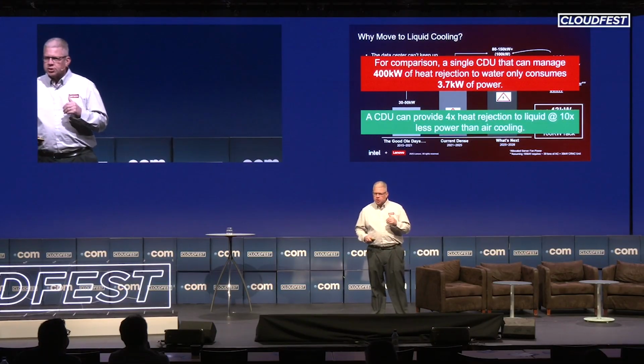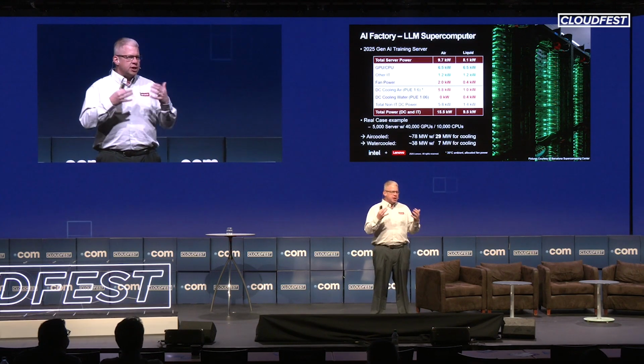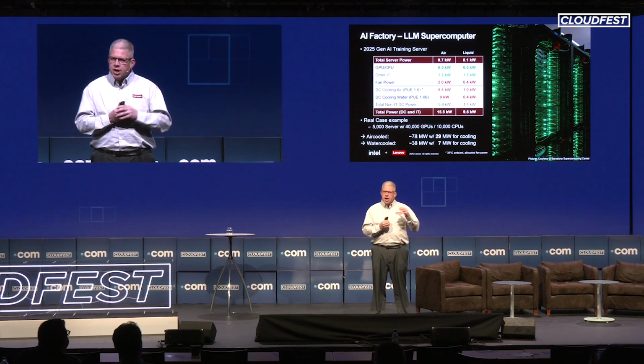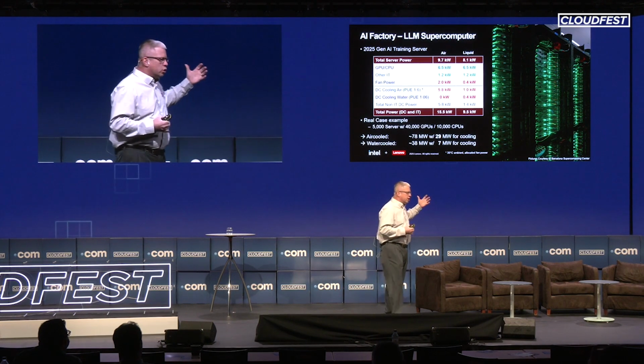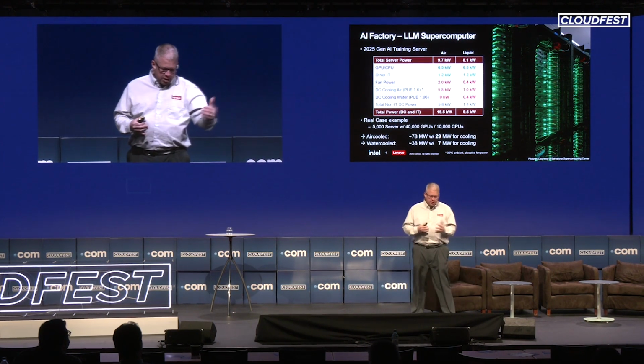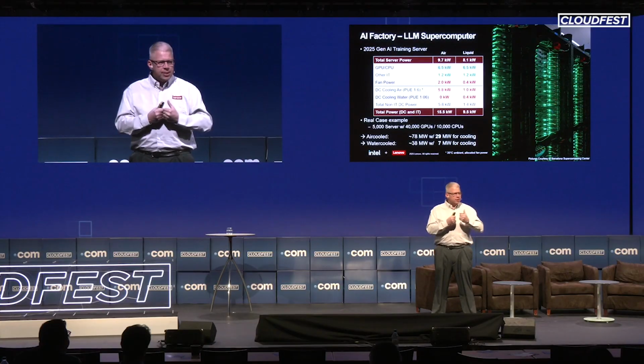Now, as you start to talk about where we are with a lot of the GPU servers folks are using for AI, some real world projections: the actual server itself is somewhere around 10 kilowatts on average. If you look at an air-cooled system, that's about 2 to 3 kilowatts just to remove the heat. If you take that same server and make it liquid - we have examples of these inside our booth - that takes it down to about 2 kilowatts, somewhere thereabouts. So removing about 20% of the power required to actually cool and operate that system.